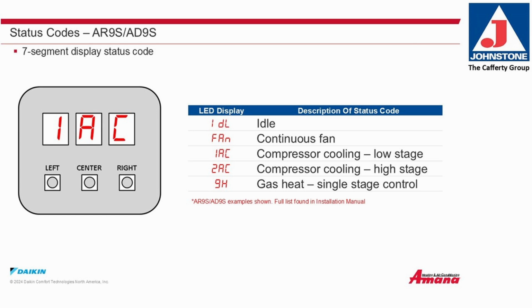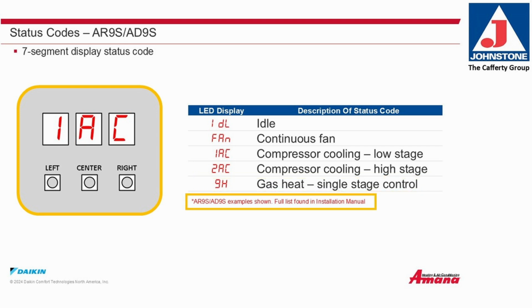Status codes displayed on the AR9S, AD9S furnace. 7-segment display status code. IDL, the system is idle. FAN, we are running continuous fan. 1AC, the compressor is running in cooling mode, low stage. 2AC, the compressor is running in cooling mode, high stage. GH, which looks like 9H on the display, is for gas heat single-stage control. The examples shown above are from an AR9S, AD9S furnace. The full list of codes can be found in the installation manual.